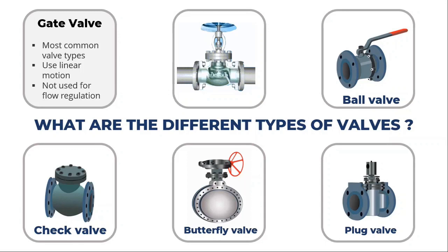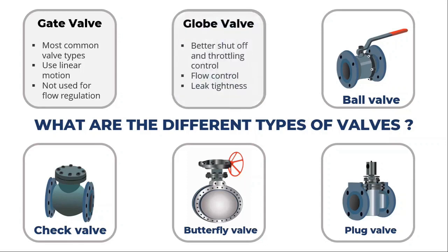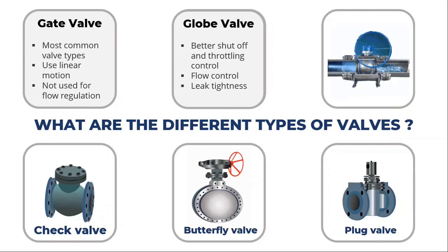A globe valve typically has a spherical body with a stationary ring seat and a moving plug element. The fluid flow is controlled, stopped, and started using a globe valve. Globe valves are employed in systems where leak tightness and flow control are both required. A globe valve offers superior shutoff compared to a gate valve.